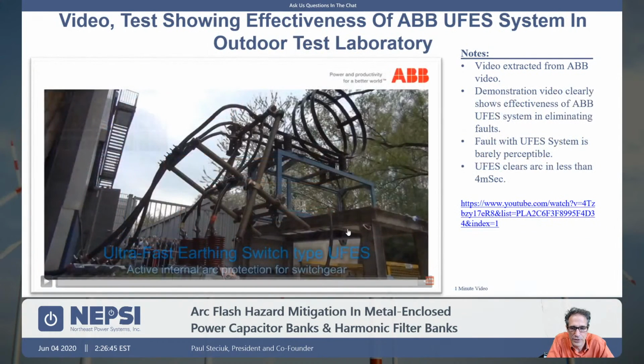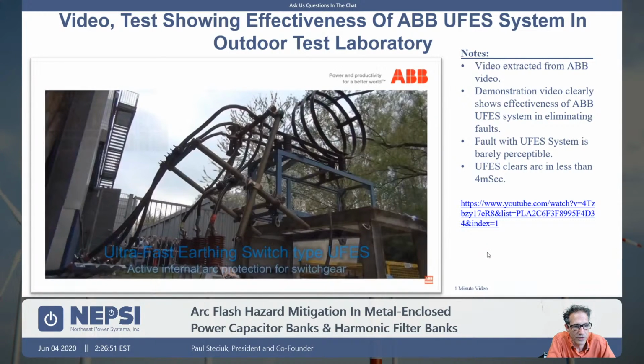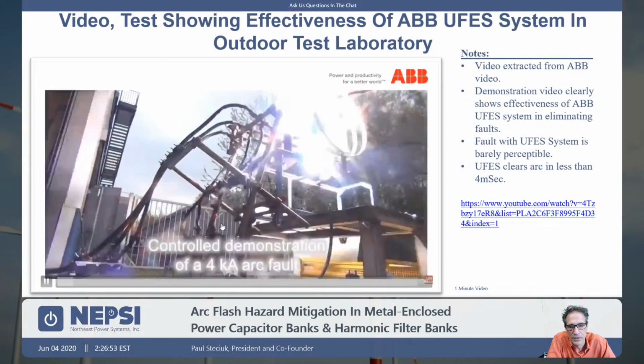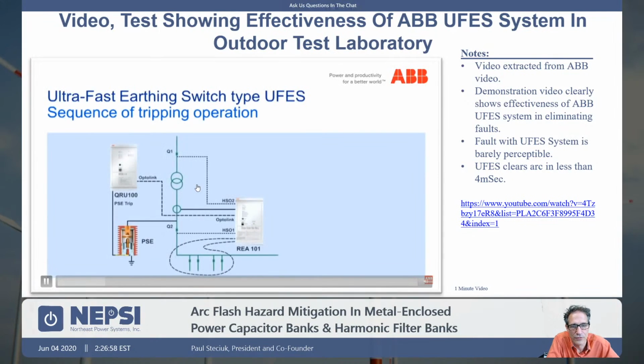So here's another video. This is just a 1-minute video, and it also shows how the system operates. It's another visual. In this case, we're showing an arcing event that does not have a UFES system. Here you can see how the system works. There's the power switching unit here. You have the bus structure here with a fault. There are fiber optics that sense the fault and current sensors that sense the fault, so it's an arc detection.